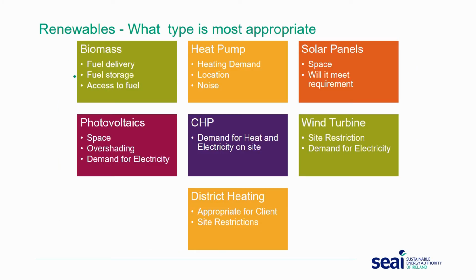So obviously there's a number of things that you should be considering. If you look at biomass, have you got adequate storage? How are you going to get the fuel supply? Heat pumps operate efficiently at a low temperature, so is the system applicable to it? You can't be sizing your radiator in a traditional way. You'd have to be sizing it as a low temperature radiator. Or if you have an air conditioning system, you shouldn't use fan coil units because they'd be operating at a higher temperature.